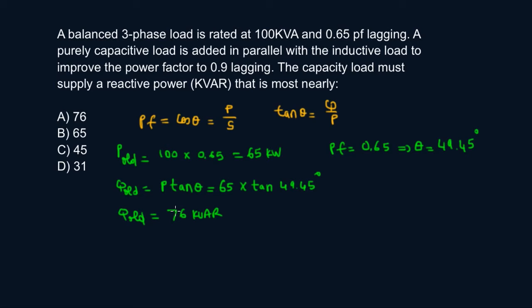Now when you add it, your real power does not change. Your real power does not change. So let's use a different color here. Let me use red. So my new power is still the same thing as my old power. It does not change at all. It remains constant. So P new is P old. So I still have 65 kW. What's my new power factor angle? My new power factor after I add the capacitor, that's 0.9. So this is where I'm trying to go. I'm trying to go to a 0.9 power factor.